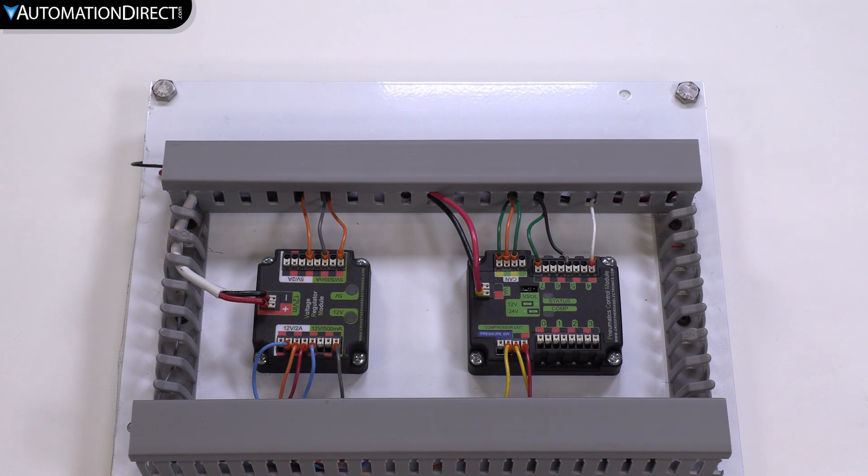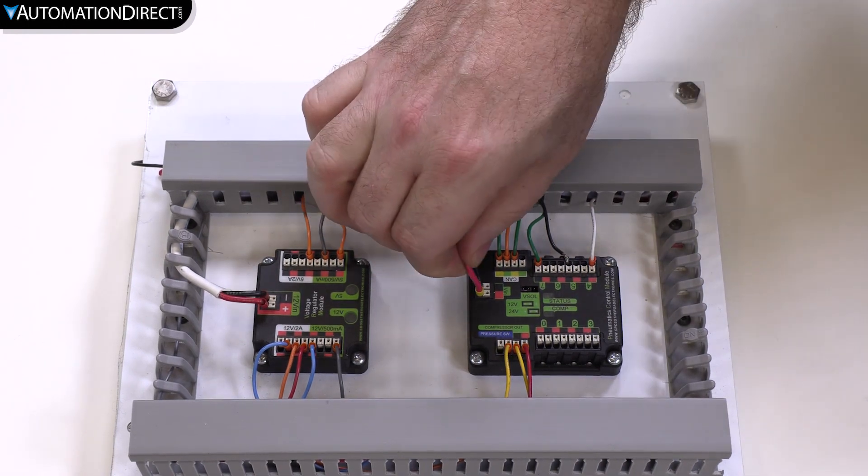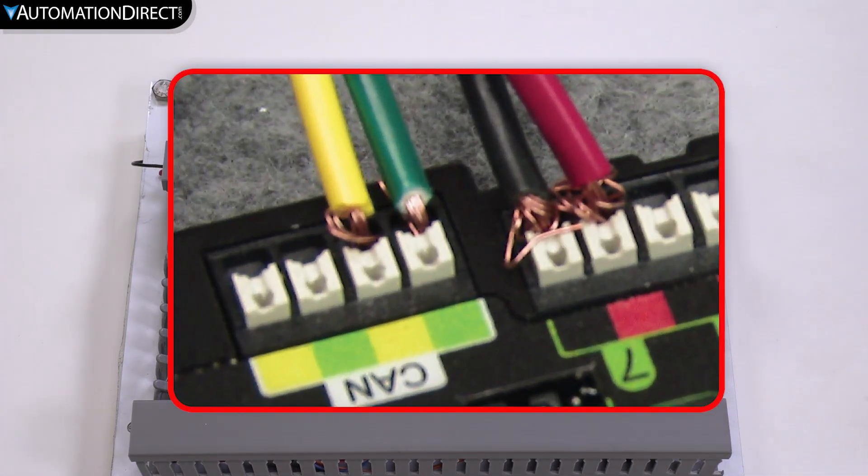If the ferrule is applied correctly there will be no copper showing and this wire can be inserted and removed multiple times without having the wire turn into a mess like this.